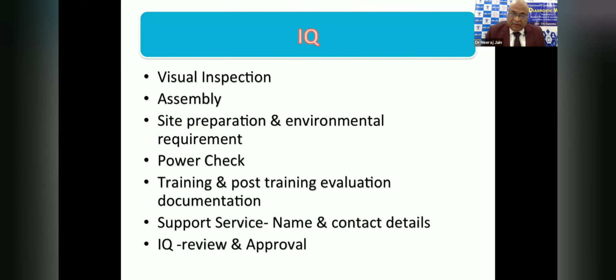Now, at the time of installation, the company person comes to your lab, opens the box and takes out the machine. Inspect the machine. If you have ordered a new machine, is it really new? It should not be refurbished, old, or damaged from any side. Then when they are assembling different parts, look at how they are assembling. And you have already ensured site preparation and environmental requirements are okay. If a deionized water plant is required, you have checked that it has been installed, and water quality, pH and resistivity are okay. You have already checked power: you have appropriate voltage, uniform power supply, online UPS, and earthing is okay, and the wire is properly connected through the power plugs with the socket.